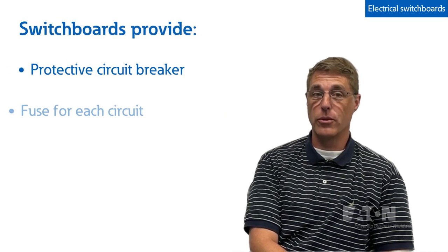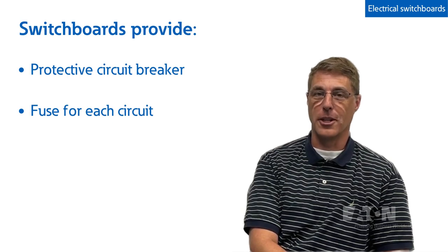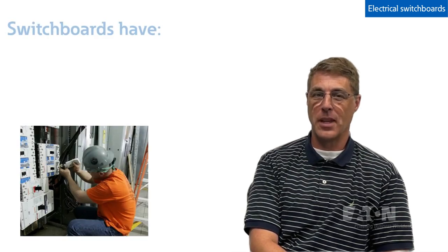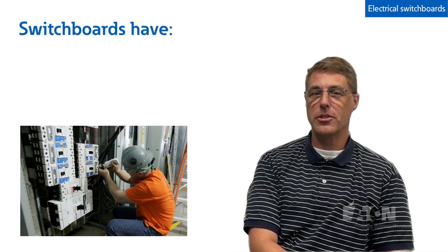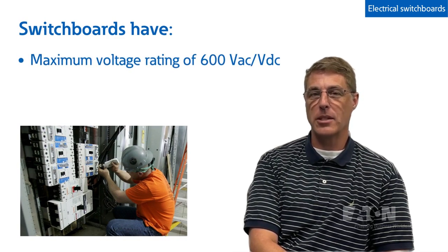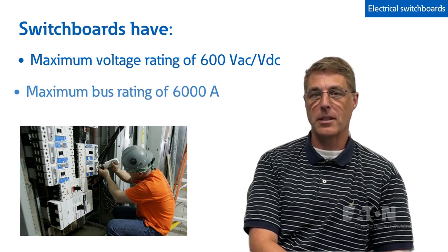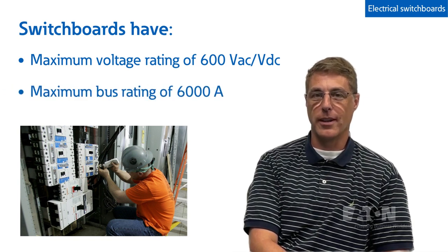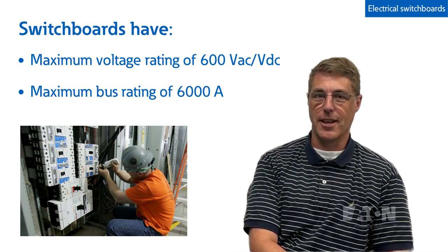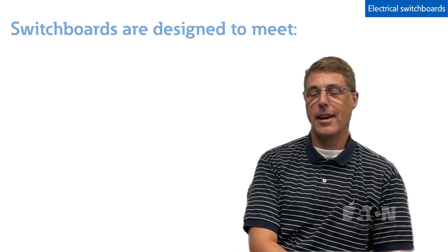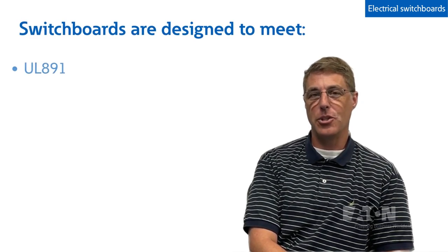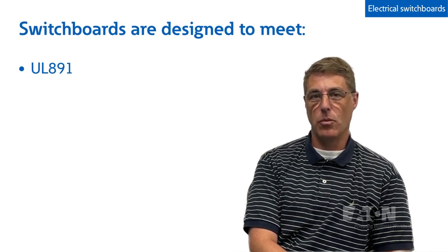Switchboards typically have a maximum voltage rating of 600 volts, either AC or DC, and a maximum bus rating of 6,000 amps, and are designed to meet UL 891 and NEMA standard PB2.